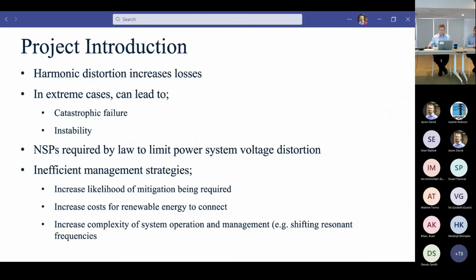It's important that NSPs have a good handle on the voltage distortion that exists on their power system, and it's also required by law that power system harmonic voltage distortion is managed. Inefficient management strategies that are commonly in use are capable of increasing the likelihood of mitigation required by customers, ultimately increasing costs for renewable energy and any connecting customer. This can lead to increased complexity of operation and management of harmonic distortion in the network, ultimately leading to things like shifting resonant frequencies and impacting the wider connected area.